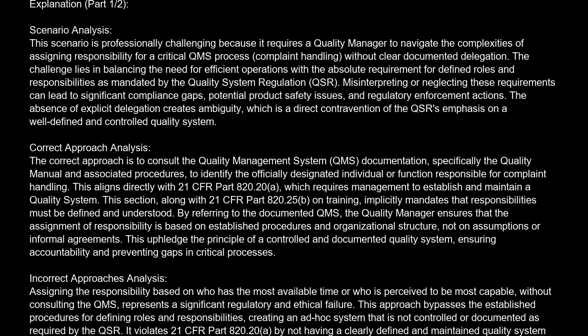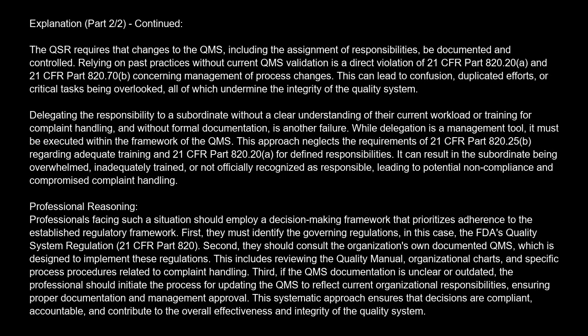Ethically, it can lead to a lack of accountability and potential neglect of critical tasks, impacting product safety and patient well-being. Assuming the previous incumbent's responsibilities automatically transfer to a new role without formal QMS updates is also a failure. The QSR requires that changes to the QMS, including the assignment of responsibilities, be documented and controlled. Relying on past practices without current QMS validation is a direct violation of 21 CFR Part 820.20(a), and 21 CFR Part 820.70(b), concerning management of process changes.